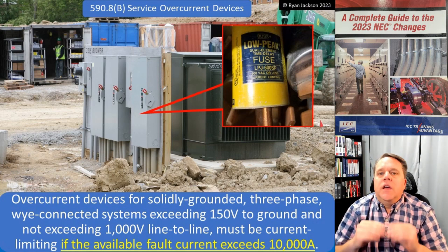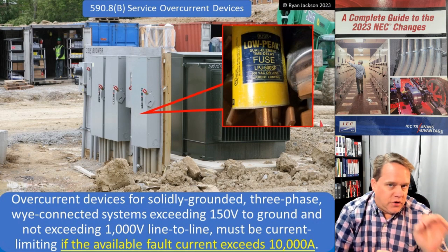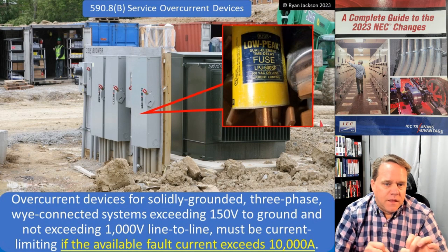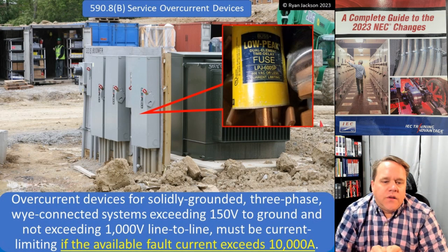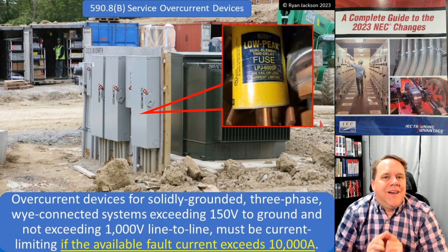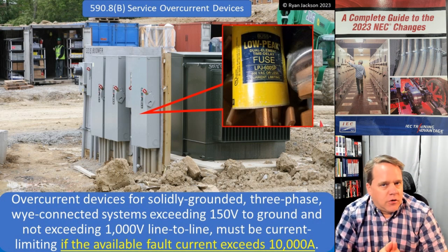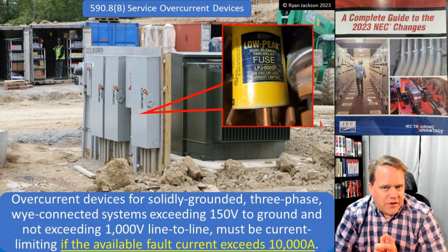So if you have, for the States, 277/480 for your temporary service, then at the service disconnect, the overcurrent device must be a current limiting device — but now only if the available fault current exceeds 10,000 amps.